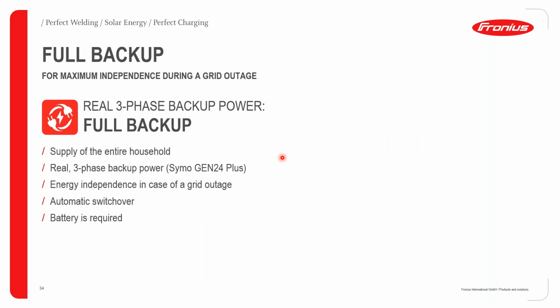In terms of a full backup, this is also possible with the Gen 24 inverters. Also, a very special feature is that the Gen 24 inverters, the three-phase models, are one of the only very few inverters in the market whereby you can get a real three-phase power backup output. Most of the other inverters require at least 3 inverters connected in series for you to get three-phase output from the inverter system as backup. So with this kind of installation, it will be very easy for you to configure a real three-phase backup for small offices or small factory setups. And therefore, this would ensure that you get maximum energy independence from the grid.